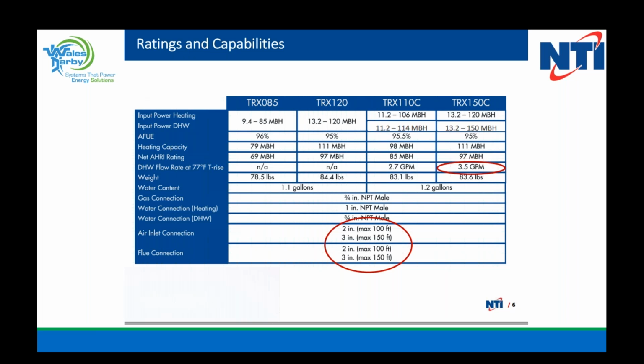Thanks, Jim. Right. A 12-foot run of baseboard at 580 BTU output, that's 6,960 BTUs. Okay, so if it's something that small, we really don't want to oversize our equipment. One other thing with this boiler, this is set from the factory at its air intake and exhaust for 2-inch piping. We can go up to 3-inch piping. So you can see at 2-inch piping, we can go a max of 100 feet for inlet and exhaust. And on the 3-inch, you can see a max of 150 feet. So that gives us a lot of flexibility.